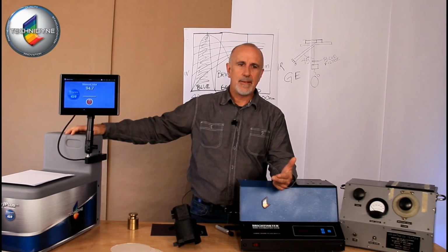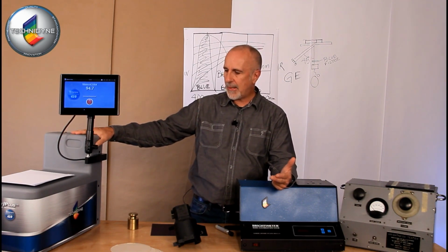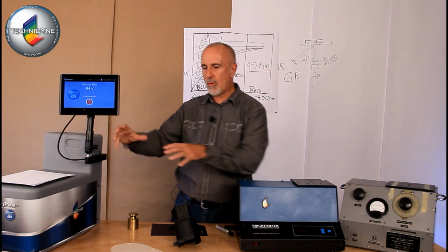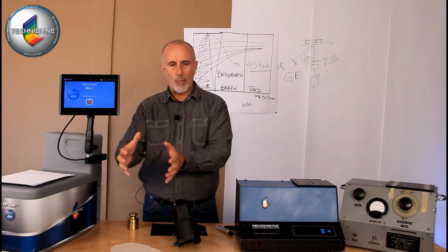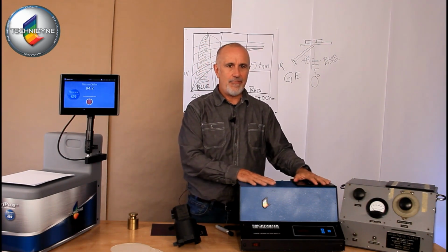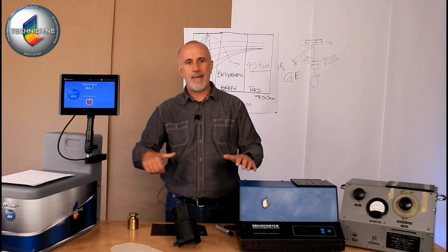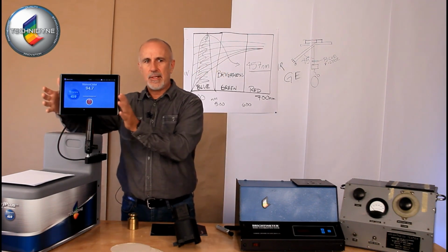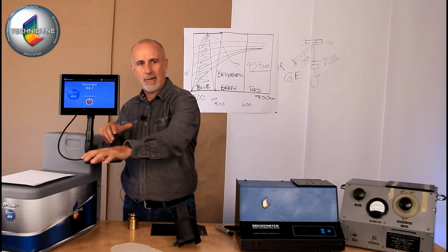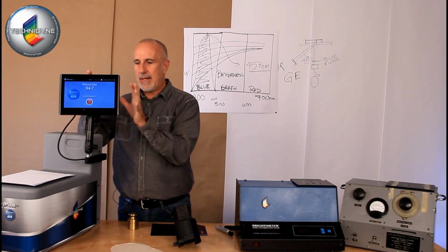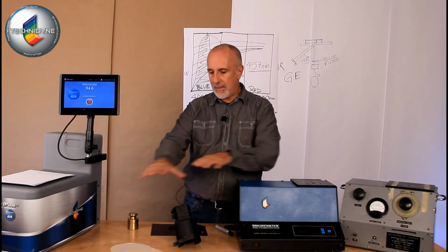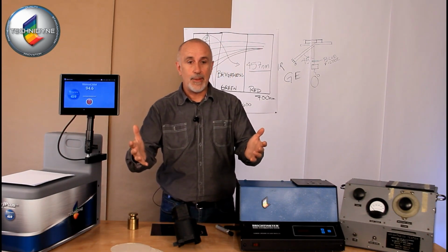When we put together the TAPPI brightness instrument in the Test Plus package, we used some different technology where we mounted the screen externally so that you could orient the instrument in whatever way you want it to best suit your application, as opposed to in the past where we kind of had fixed orientations with that. Now, with this, you're able to adjust the screen, move the instrument 90 degrees, move it the other 90 degrees, move it 180 degrees, adjust the screen to that so that you can more effectively measure your sample in the different conditions where we measure TAPPI brightness.